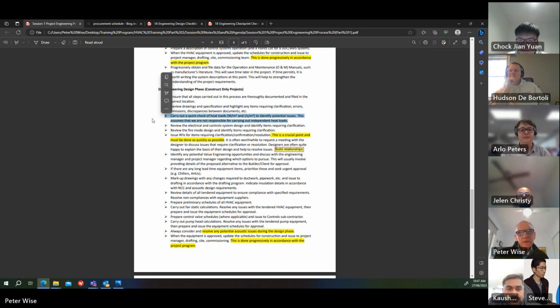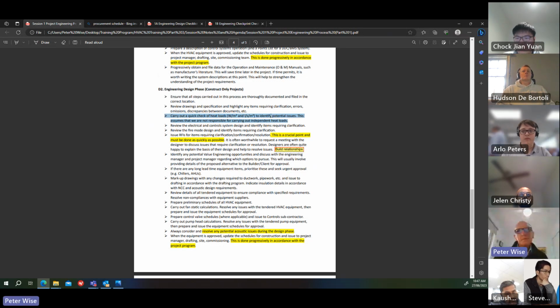It's worth doing a quick check of the air conditioned areas on a watts per square metre and litres per second per square metre basis, just to see if there are any potential issues. For instance, in the extreme, you look at an office area and it works out at 250 watts a square metre. That doesn't seem right, because it's normally not that high - for a normal office with one person per 10 square metres or so, it would normally be less than 150. So if it's 250, something might be wrong, someone's made a mistake. We're not doing heat loads, but it's good to do these checks and get them clarified.